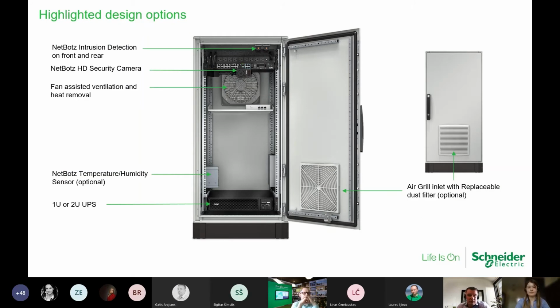This slide shows the internal view of the enclosure and what could be configured. It's an enclosure with 19-inch rails mounted on the sides for IT equipment. On the bottom, to support clean and uninterrupted power, we have a pre-integrated UPS. Inside the rack, we also have a heater to maintain temperature in case the outside temperature is too low, and to eliminate condensation that could damage electronic components. In the middle, there's a shelf that can be used to place operational OT equipment.